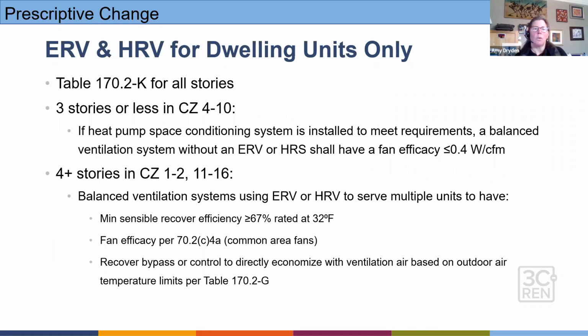Great. For ERVs and HRVs, this is really focused on dwelling units. There's a table in there. It covers all stories, but I'm just calling out a couple of nuances for the 3 stories and 4 stories plus. So if I have a heat pump for space conditioning and I'm 3 stories or less in climate zones 4 through 10, I have some fan efficacy requirements there of less than or equal to 0.4 watts per CFM. So we're looking at more stringent efficacy requirements for that condition.